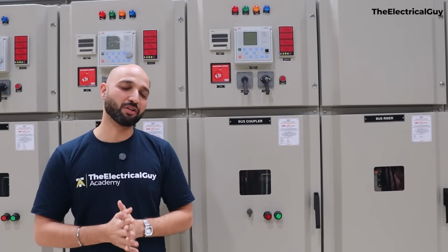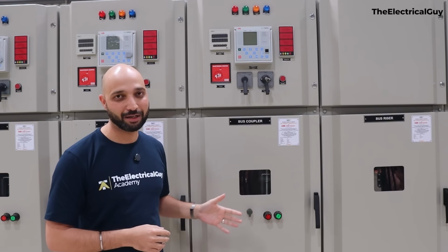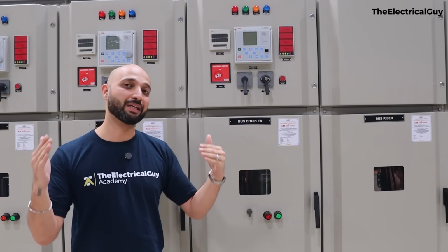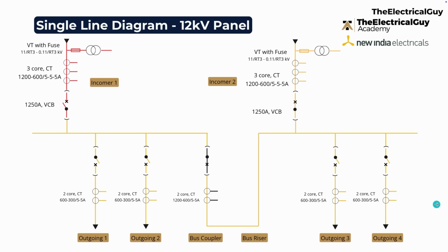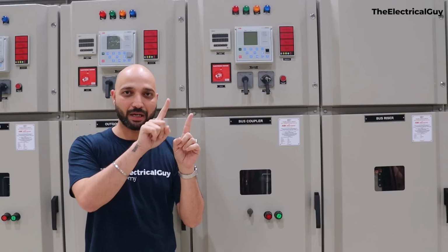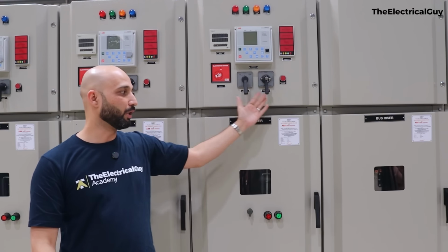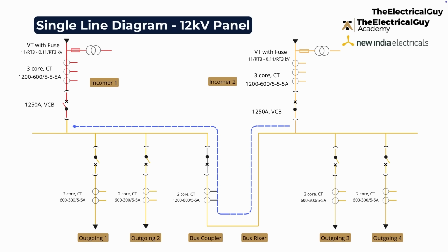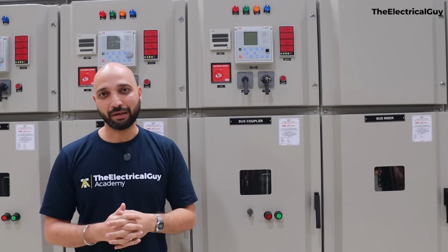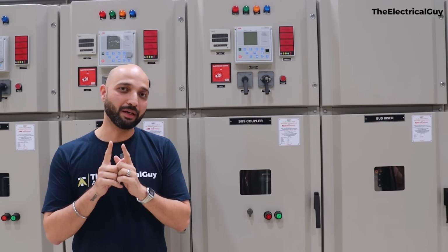And that's the exact function of why we have this bus coupler panel. As the name suggests, it helps in coupling the two bus bars or two supplies together when we want them. Now, of course, you cannot connect all those three things together. It will create a short circuit, so please avoid that. In order to close this breaker, either of the supplies, either incomer 1 or 2, must be open. Only then will you be able to connect this, and the link between the two supplies will be closed and the supply from incomer 2 will flow in the outgoing of incomer 1 as well. Thereby, we can achieve the supply reliability. And that's why we need the bus coupler in the system.